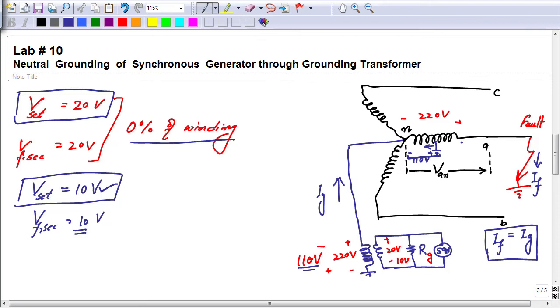So what is our conclusion about this discussion? From this 10 volt setting we can say only 50% of the winding is protected. When we had the 20 volt pickup, 0% of the winding was protected. With 10 volt, 50% of the winding is protected, because if a fault occurs from neutral up to 50% of the winding, the voltage would not be sufficient to result in tripping of the relay.